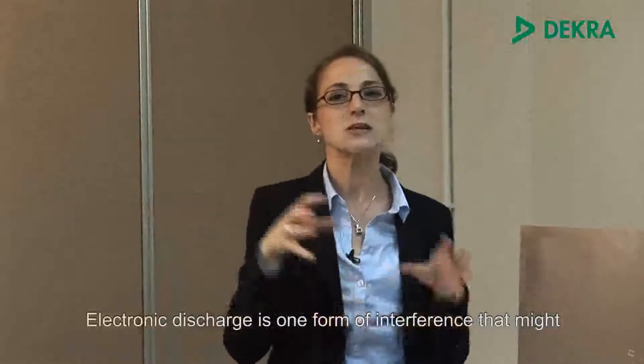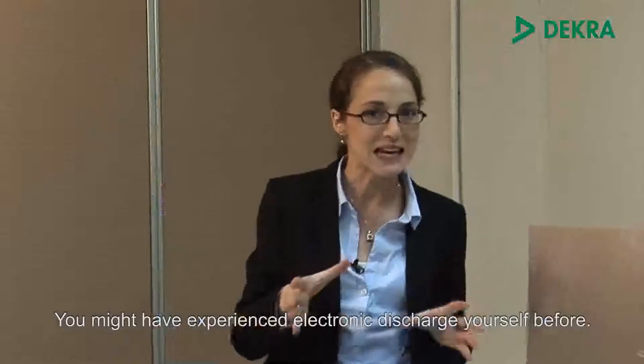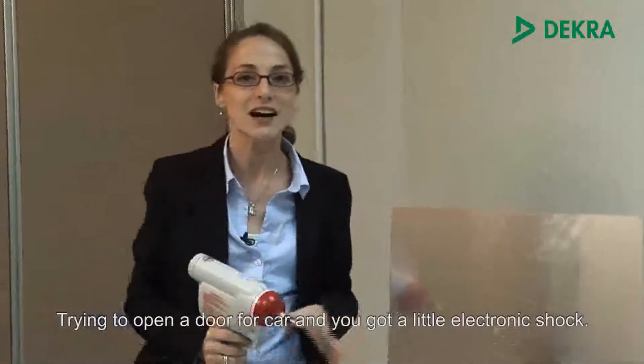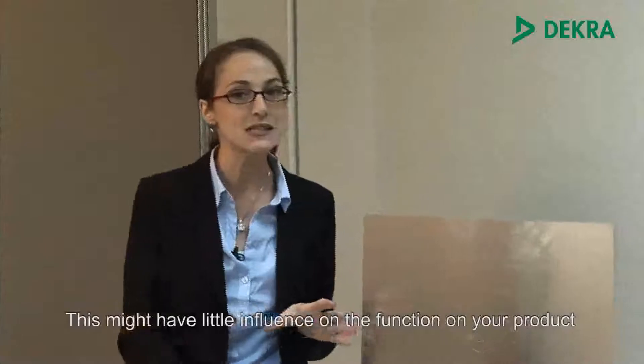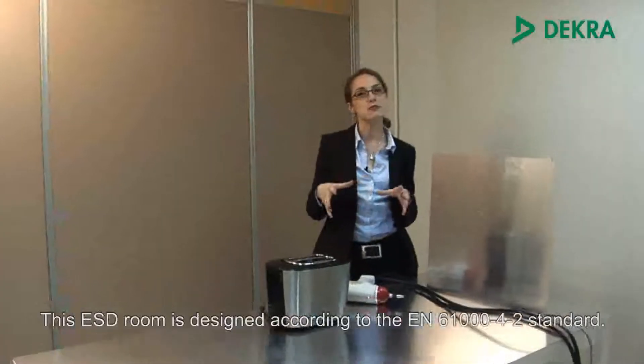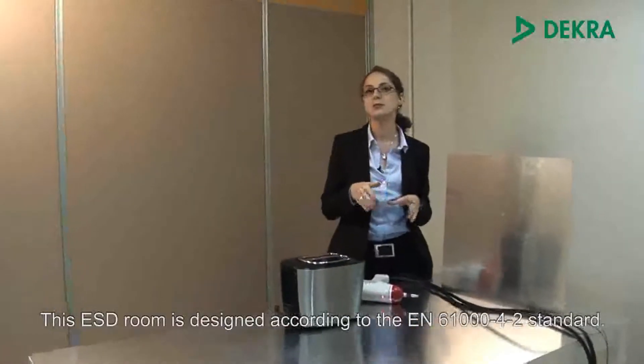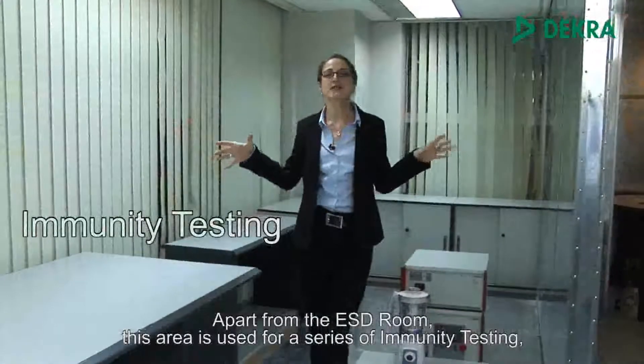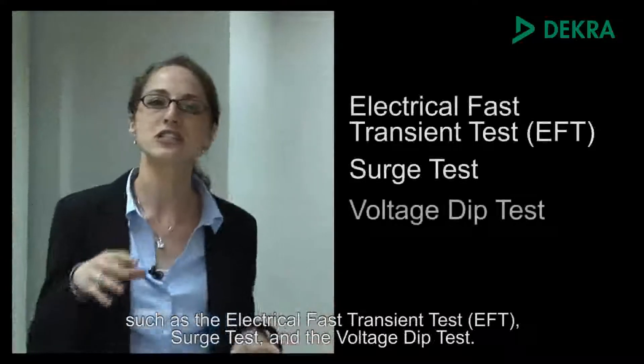Electrostatic discharge is one form of interference that might influence the operation of your electronic device. You might have experienced electrostatic discharge yourself before, trying to open a car door and getting a little electric shock. This might have little influence on the function of your product, but it might also cause abnormal function. This ESD testing room is designed according to the EN 61000-4-2 standard. Apart from the ESD room, this area is for a series of immunity tests, such as the electrical fast transient test, the EFT, surge test, or the voltage dip test.